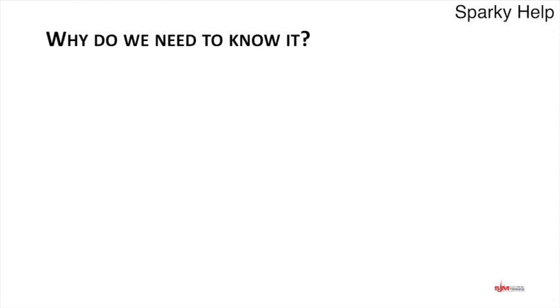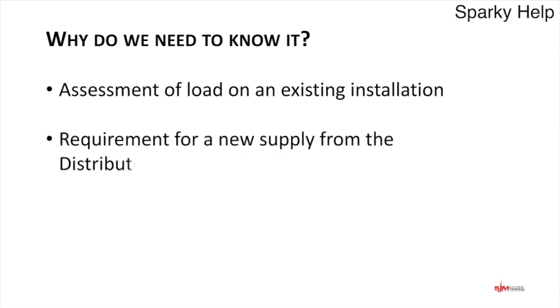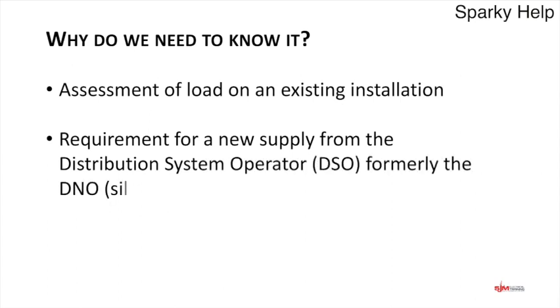Why do we need to know it? It's an assessment of the load on an existing installation. It's also required when applying for a new supply from the distribution system operator — a new term added in the BS 7671 2022 edition, formerly known as the DNO. This is your supply company, and they will often need to know what your maximum demand is if you're asking for a new supply.